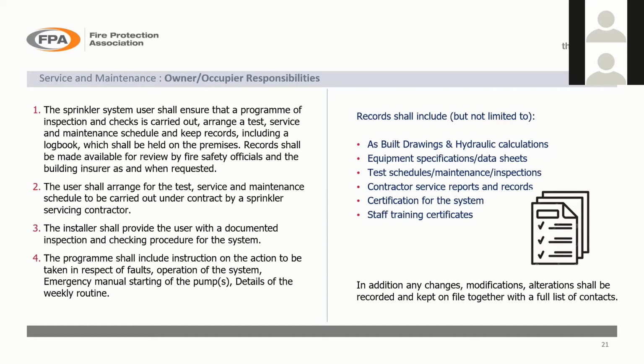And the certification is very important because, as Dale said, once you've left site and issued over the 1048 certificate, that's all that anybody else has got to go on. If they come to modify the system or change anything to the system, things like storage and that, you can work out what densities of discharge you've got from the certificates. So without that information, it makes it very difficult to tell whether your modifications are actually going to comply. And the other thing to keep is staff training certificates, to make sure that your staff have been trained to do the tasks.